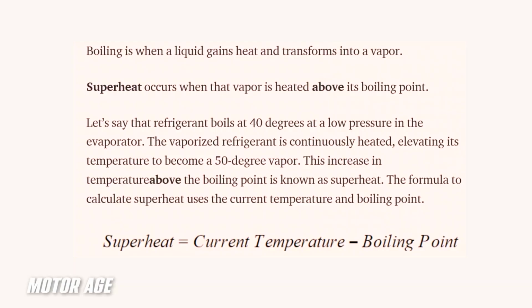So basically, subcooling is any amount of cooling that takes place to the liquid refrigerant after gas becomes liquid. Gas becomes a liquid, we call that condensation. Any additional heat loss is known as subcooling. And you can take a guess what superheat is. Boiling is when a liquid gains heat and transfers into a vapor. Of course, we've been discussing that all along. Superheat occurs when the vapor is heated above its boiling point.